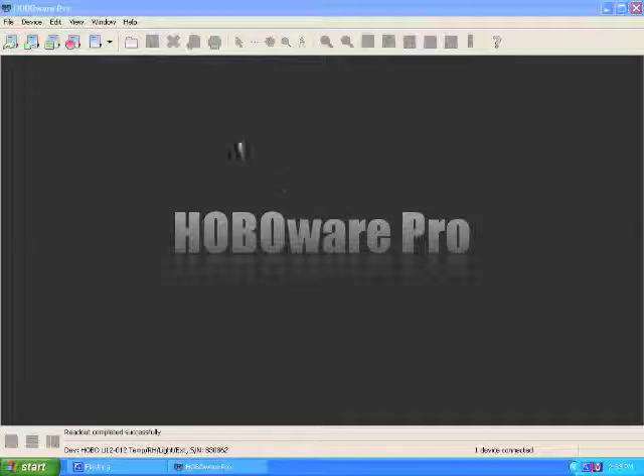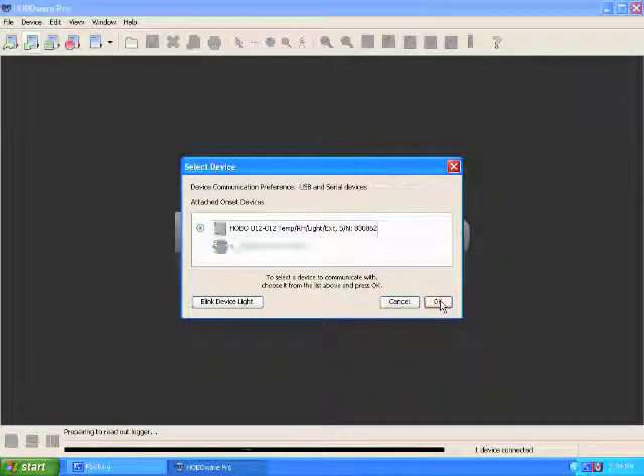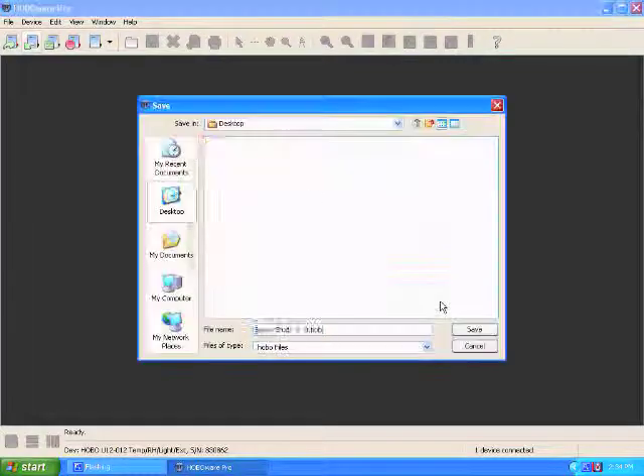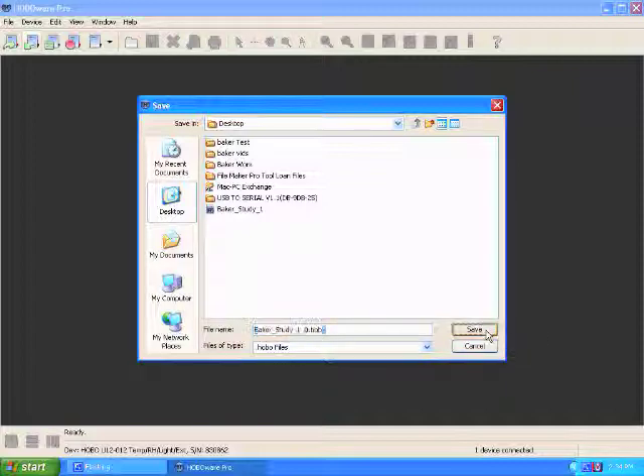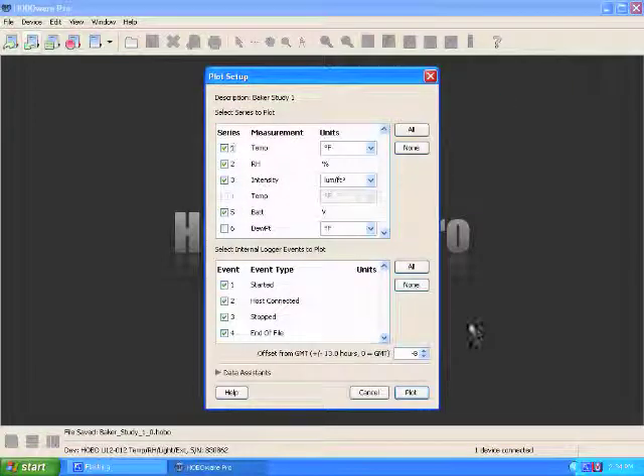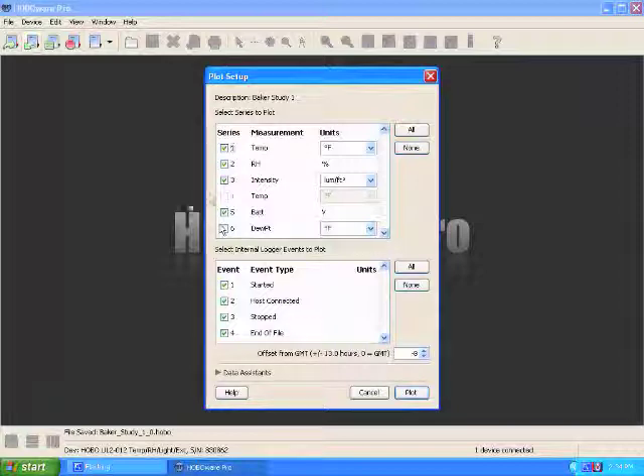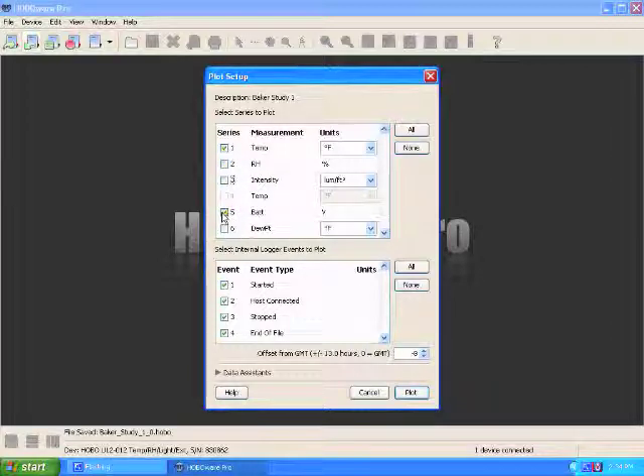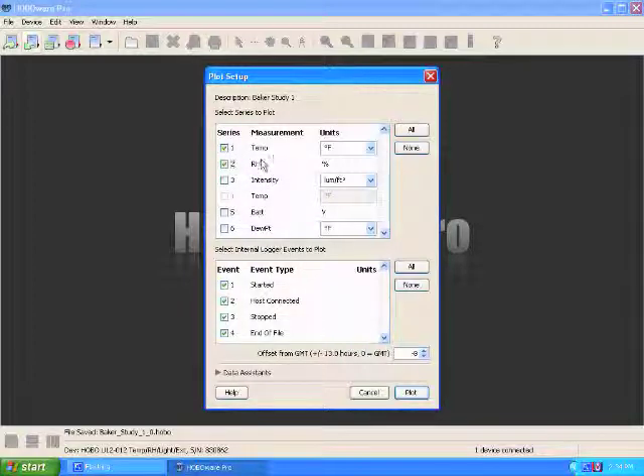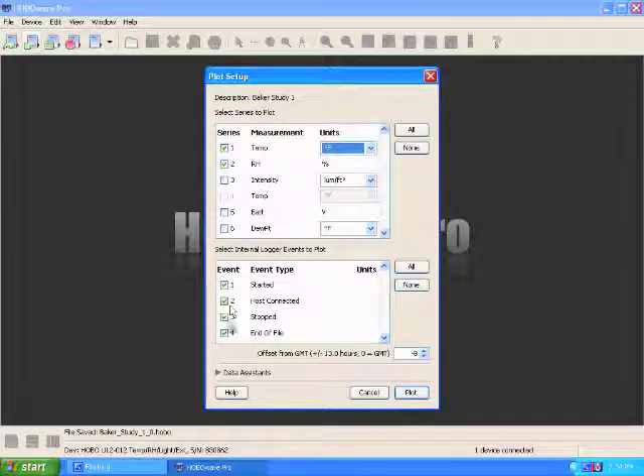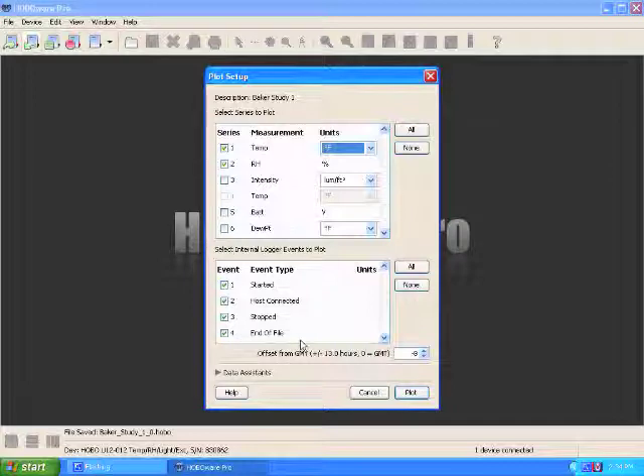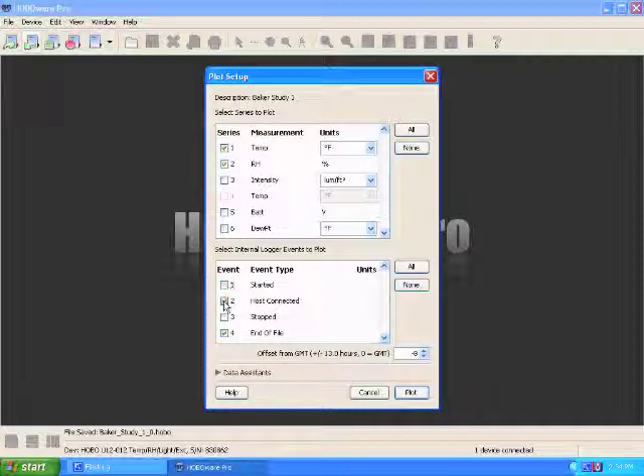So, when you're done collecting data, plug your Hobo back in and click the readout button. Once again, it will find it on your port and prompt you for a place to save it. Now here you can choose what you get to see on the printout graph. It might be useful first to just pick the units that you're most interested in seeing. I'm going to choose just temperature and relative humidity for the moment. And choose your units and so forth. This will also give a printout on your chart of all these different times when your logger started or stopped taking data. And you can turn those off if you want. They're not super useful.